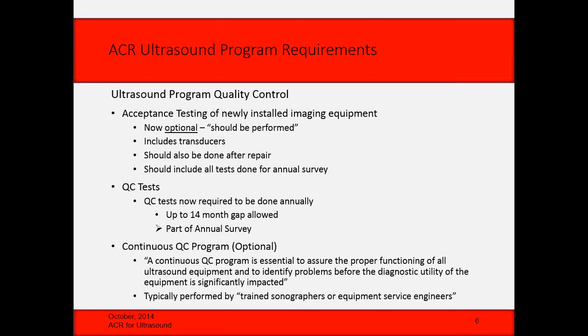One of the things that they changed is the verbiage about who does that. It now says that it's typically performed by trained sonographers or equipment service engineers. And I do know of some sonographers that actually either have some test device and they have learned how to do some of the QC tests, and they're actually doing the QC on their system. And frankly, as I'm going to talk about a little bit more, the users need to be part of an ongoing quality control program for several reasons.